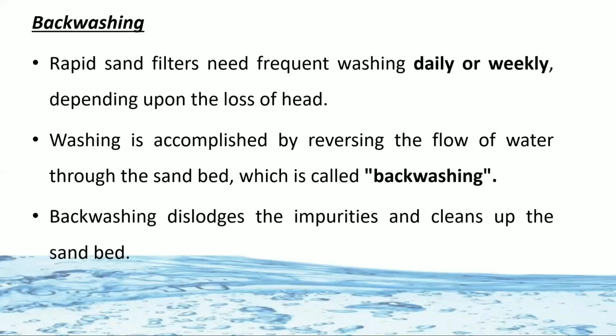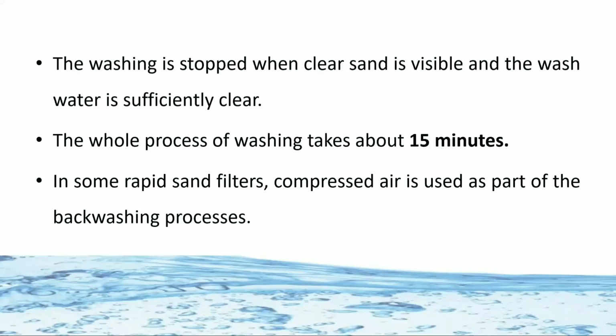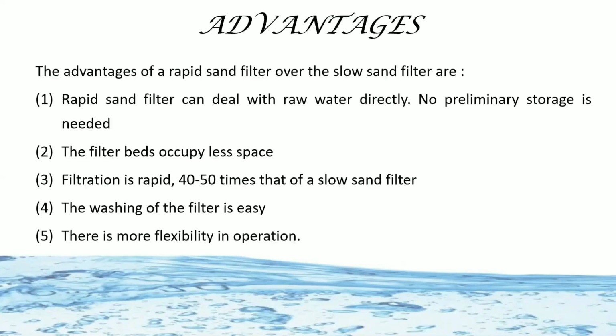For washing, the flow of water is reversed through the sand bed, which dislodges the impurities and cleans up the sand bed. The washing is stopped when clear sand is visible and the wash water is sufficiently clear. This process of washing takes about 15 minutes. Here, sometimes compressed air is used as a part of the backwashing process.